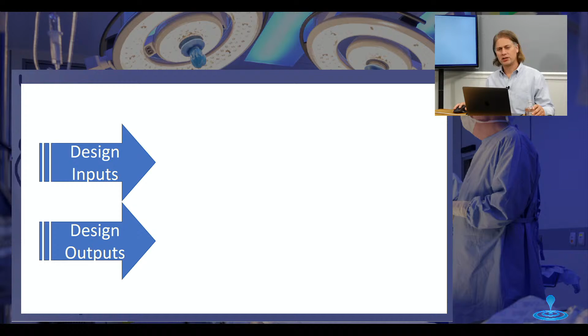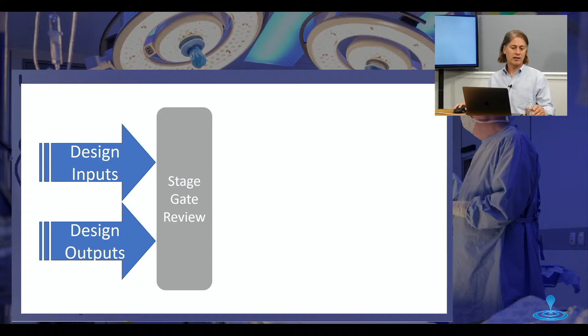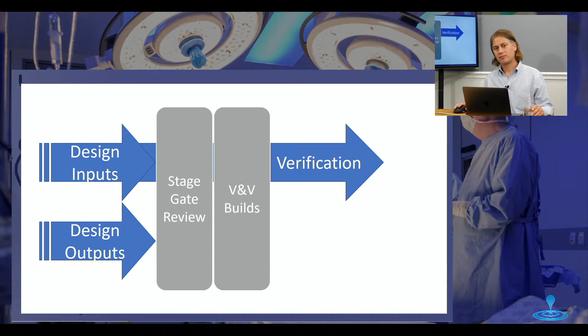Because like we said before, if you're going to do verification and validation, there are certain requirements about what it was you were testing and what you knew about it. This drives us to at least one absolutely critical stage gate review. And that could be a stage gate review that deals with both inputs and outputs. Because from there, you need to build the things under control that are going to be used for your verification and validation. Now, that doesn't mean you couldn't have been doing verification all the way through this process. In fact, there's a lot of verification you can do, and it doesn't require production representative parts. But for validation, it does.